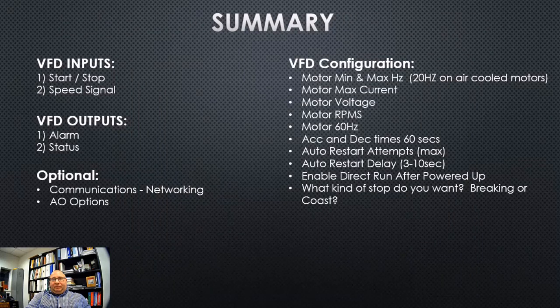So let's summarize real quickly what the inputs of a drive should be and what the VFD configuration should be. Starting with the inputs, okay, we have a start-stop signal. We have to tell it to activate or deactivate, and it has to be a binary, dry contact closure. We also have to tell it how fast that particular drive needs to run, and that's going to be our speed input signal. Those are called inputs.